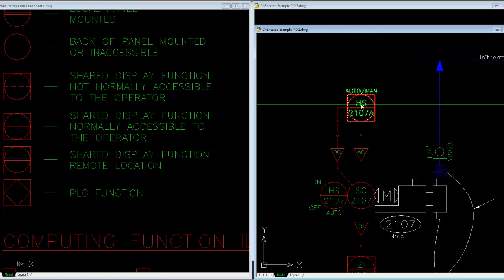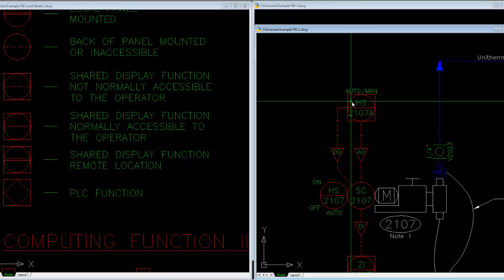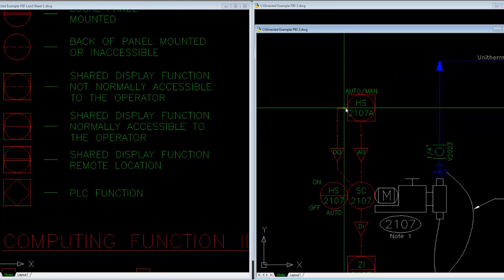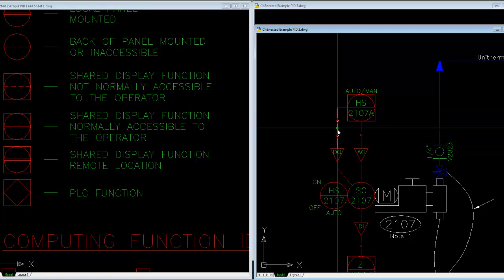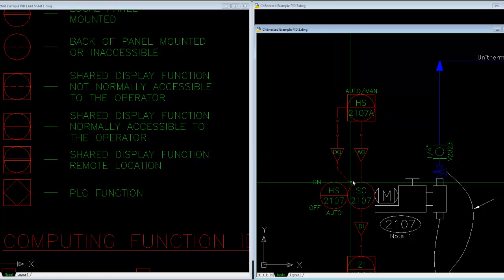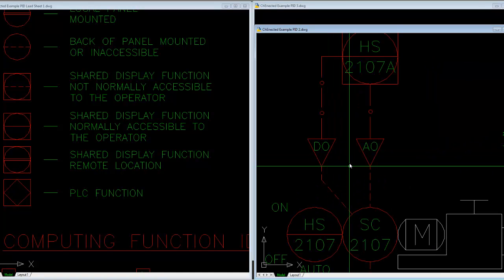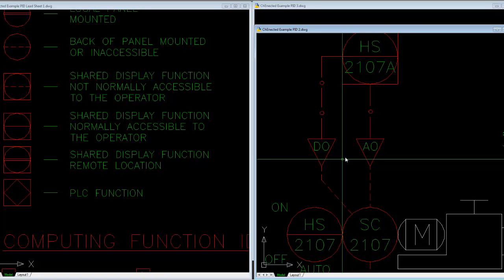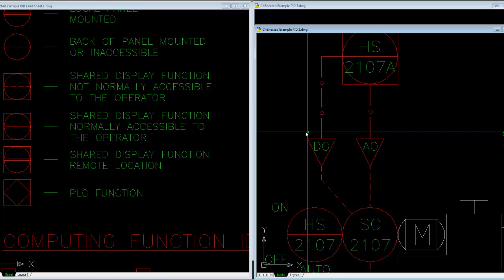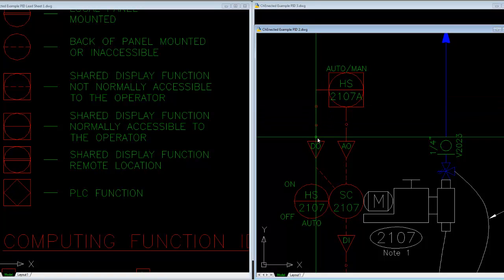Since you're interfacing with what you can see on a screen, when you click on a button to do something it sends some sort of electrical signal, interpreted first by software — which is what this line represents. The programming inside the computer interprets your click as an event; that event then runs some code. That code would presumably tell the pump to start, stop, or change speed. I use diamonds to represent the type of analog or digital signals originating from — commonly — the PLC, which is what I use in most of my plants.